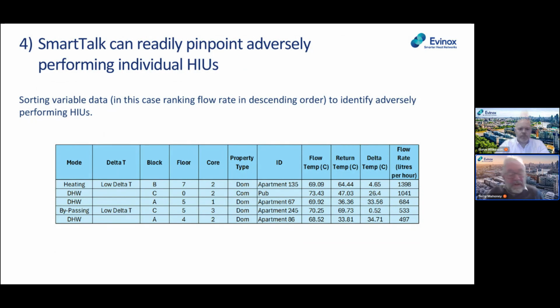Flow rate through an HIU is a good indicator of whether it's performing as it should, and delta T—the difference between primary flow and return temperature through the HIU from the heat network—is another indicator. In this example, we're highlighting excess flow rate, which implies low delta T, so we can see specifically which apartments need attending to.